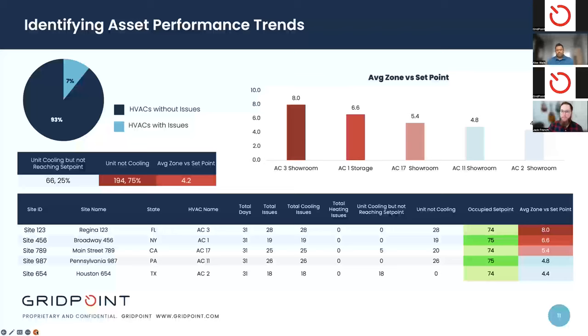So one of the most important metrics we use in quantifying a unit's performance is the zone versus set point delta - how far away is the zone temperature from the configured set point. What does that mean in terms of the HVAC's health? Let's qualify it and figure out a plan to service it before it becomes a more significant comfort concern or equipment-related reactive failure.